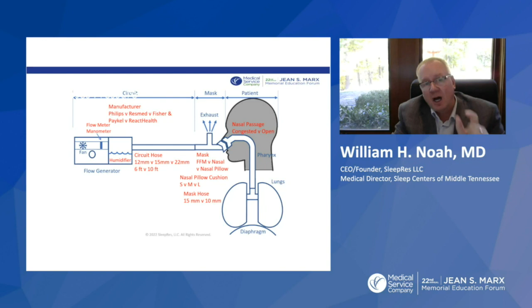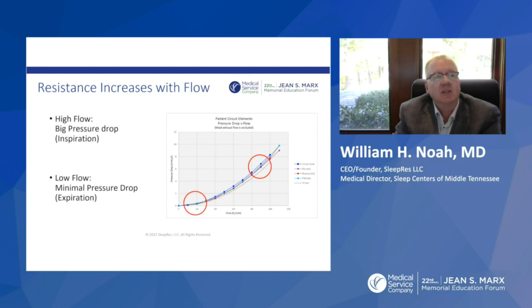Now, we talked about resistance increases with flow. And of course, it's turbulent flow, so it's going to be parabolic. It's going to be curved like this. And what that means is at high flow, you've got flow on the x-axis below, and you've got pressure drop, the change in pressure, over on the y-axis. And you can see at high flows, you have a lot of pressure drop out here. But the great news is when they're parabolic and it's turbulent, at low flow, you don't have any pressure drop. And we're going to use that to our advantage to help make CPAP more comfortable for our patients. And that's what the VCOM does. We'll talk about it in a bit.